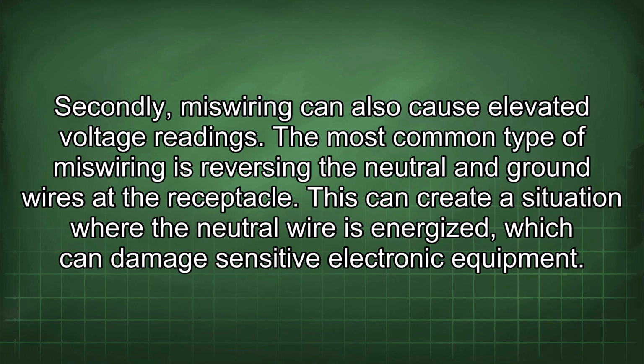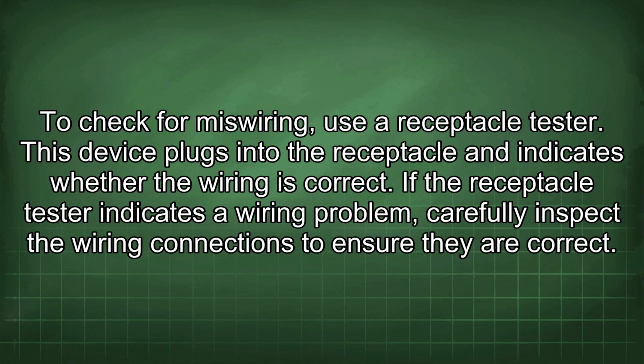The most common type of miswiring is reversing the neutral and ground wires at the receptacle. This can create a situation where the neutral wire is energized, which can damage sensitive electronic equipment. To check for miswiring, use the receptacle tester. This device plugs into the receptacle and indicates whether the wiring is correct.